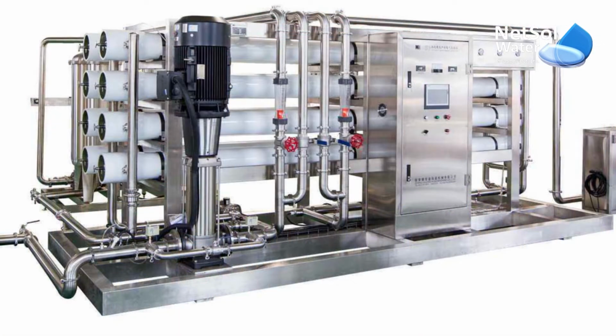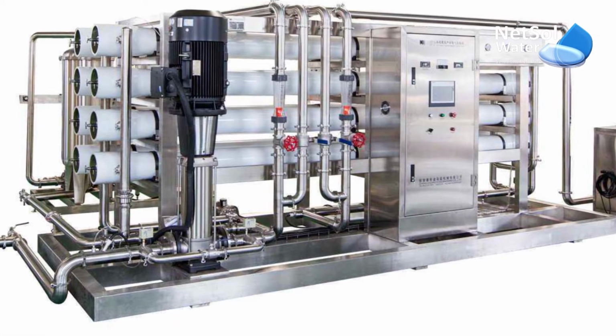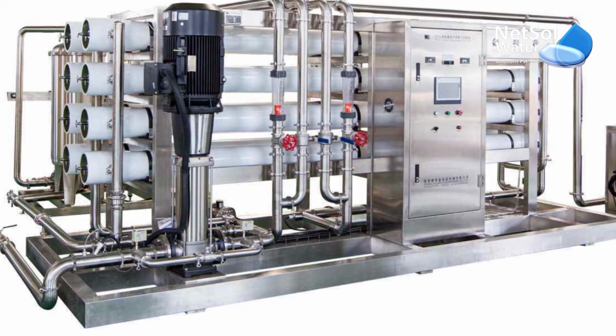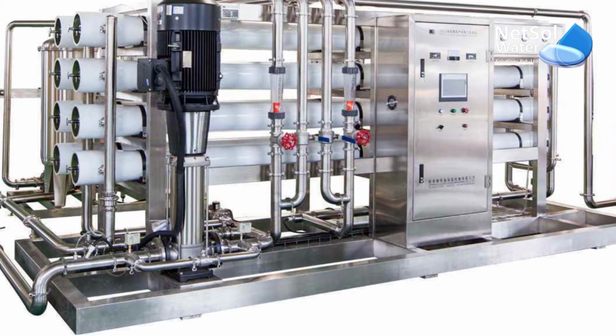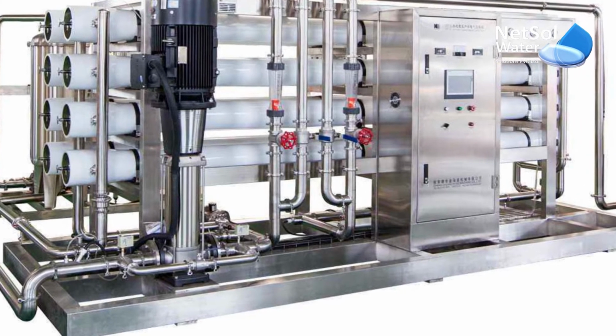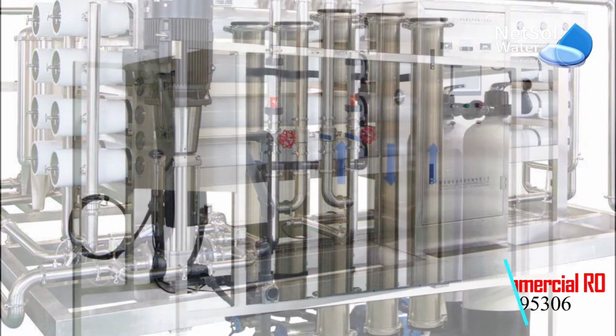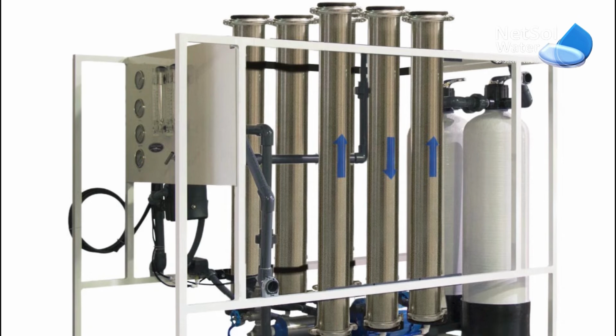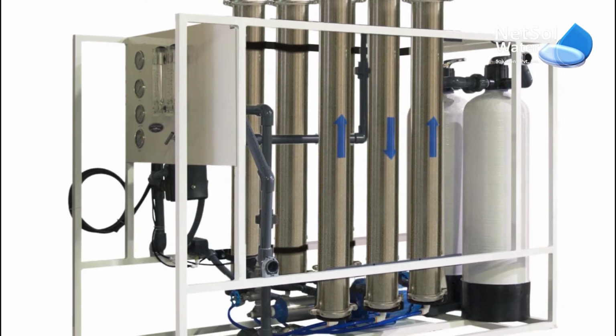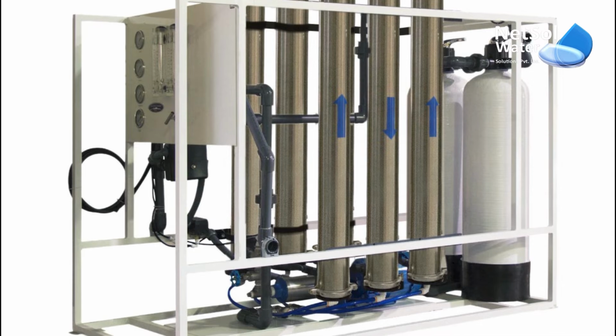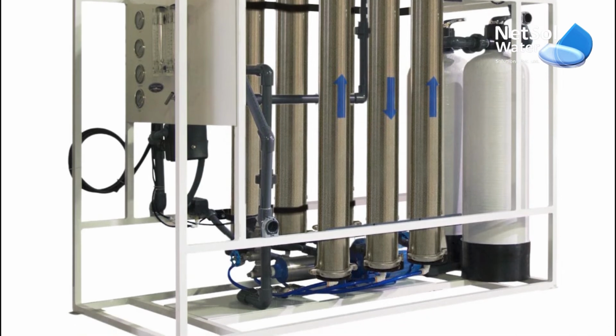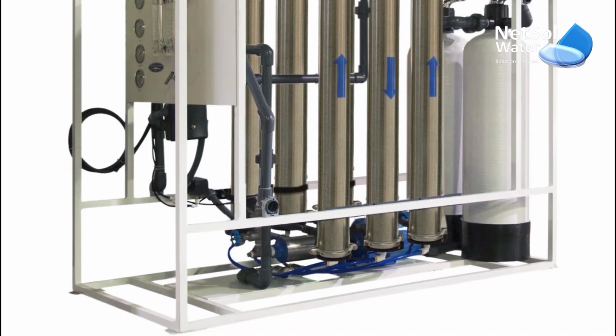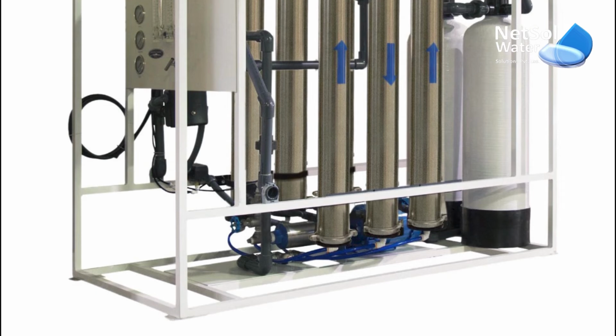We all know, and it goes without saying, that errors arise when these three criteria are overlooked or disregarded. These problems can arise in your commercial RO plants where the plant is poorly designed or incorrectly installed, or when the input water is insufficiently treated to remove chlorine, calcium, and magnesium, or when the membranes are not regularly cleaned or replaced, or when the plant pumps are not adequately maintained.